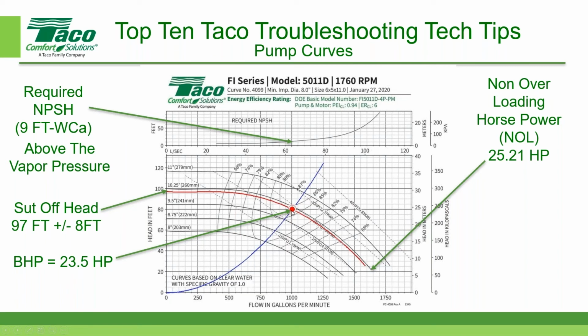That comes right off of the pump curve right here. But they're telling me they're running around 750 gallons per minute, and it's around 92 feet. So that means that my horsepower should be closer to, in this particular case, fairly close to 20 horsepower.